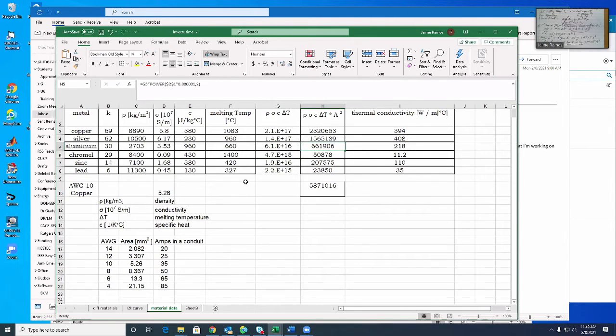So look, it's very sensitive to the area, to the cross-sectional area. Now I put here, for example, the area of different wires and conductors that we use in electrical installations. So number 10, which is good for 30 amps in a conduit, is 5 millimeters square. Number 8 is 8 millimeters square.